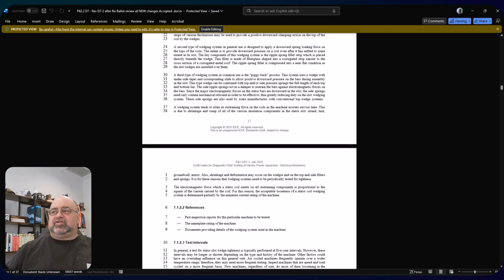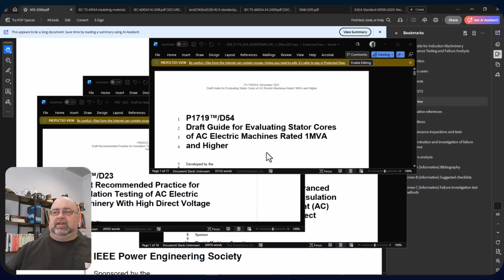Now that's important to understand, and we're going to get rid of this now and move on to the next one. But it's important to understand that the visual inspections carry more weight than your standard electrical inspection. So if I have a surge test performed, but I see a damaged insulation system, which carries more weight? I've had people argue with me to move forward because it passed the surge test. Well, I'm sorry—when it goes into operation, it's going to fail rapidly because visually it's already failed. Dry and brittle and other conditions are very, very important to notice.